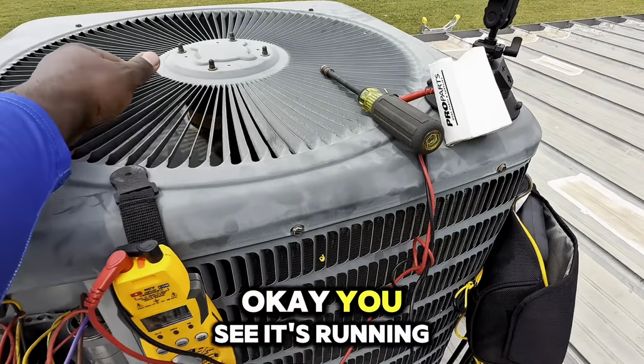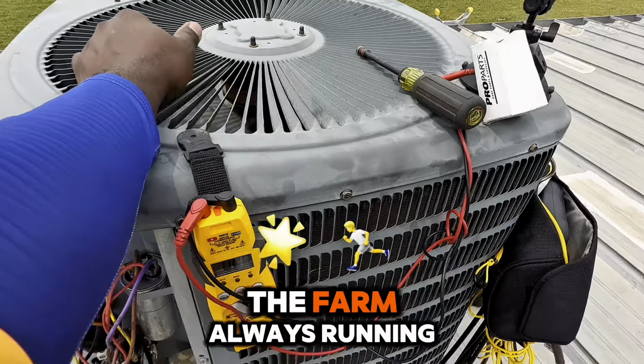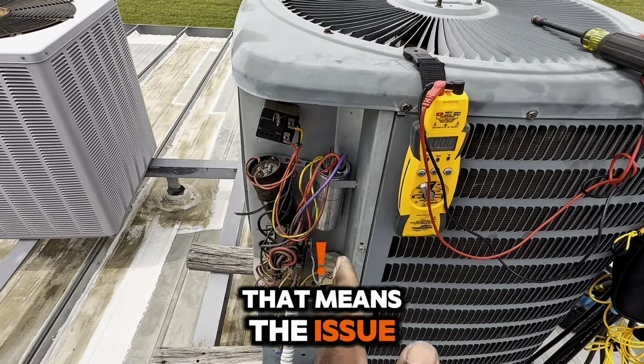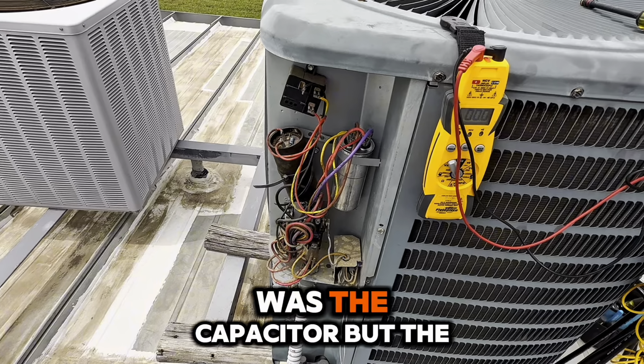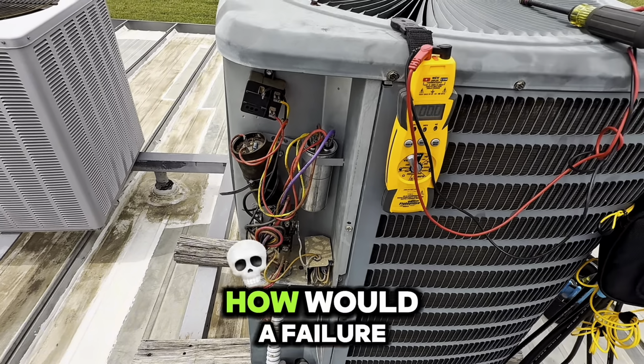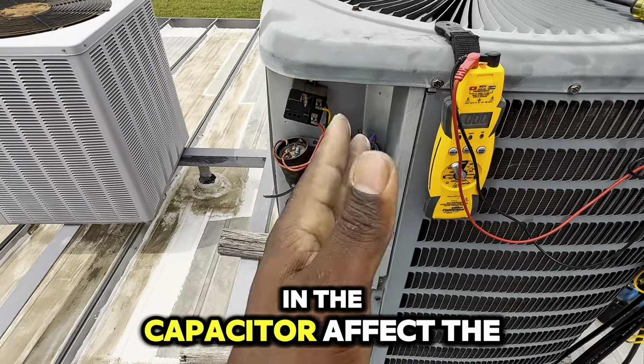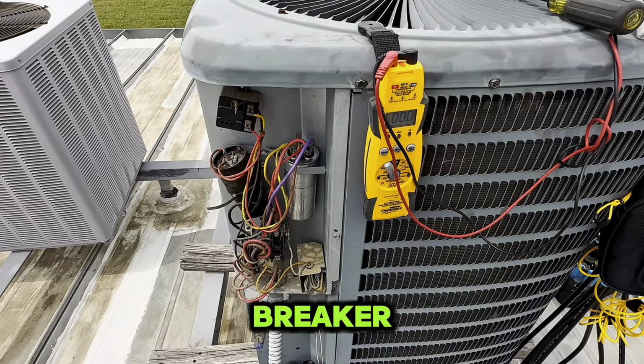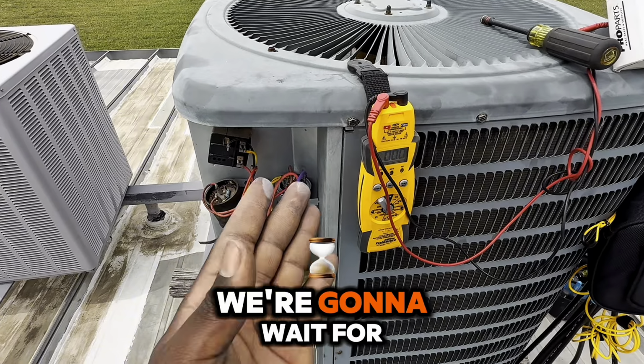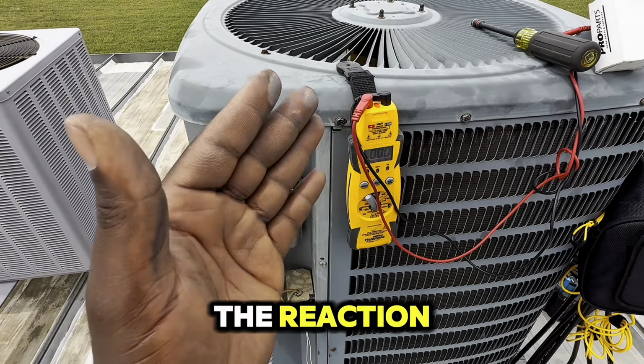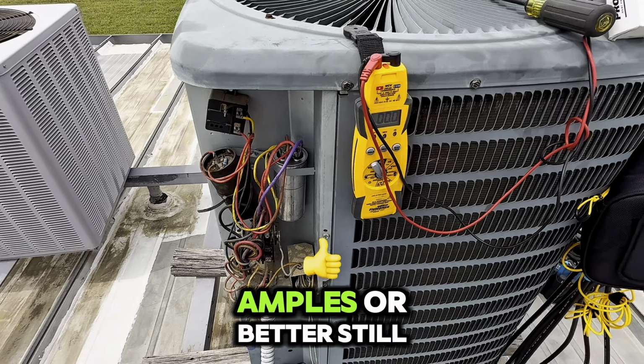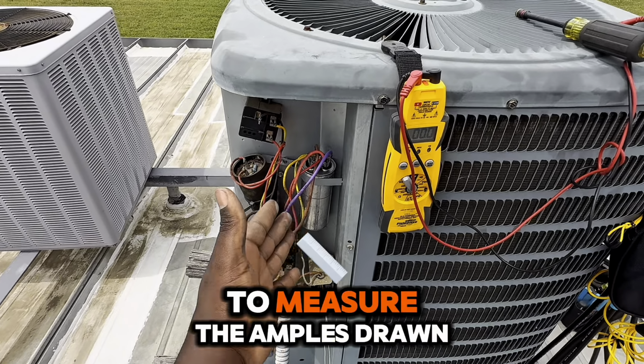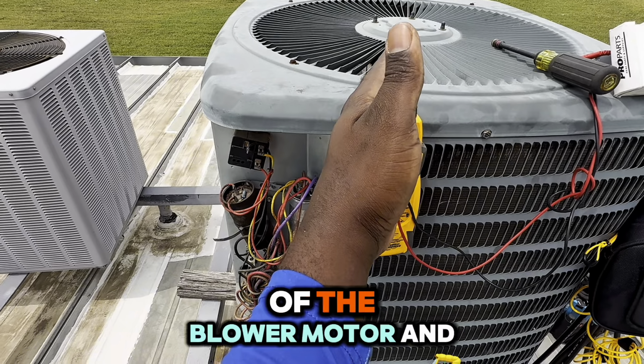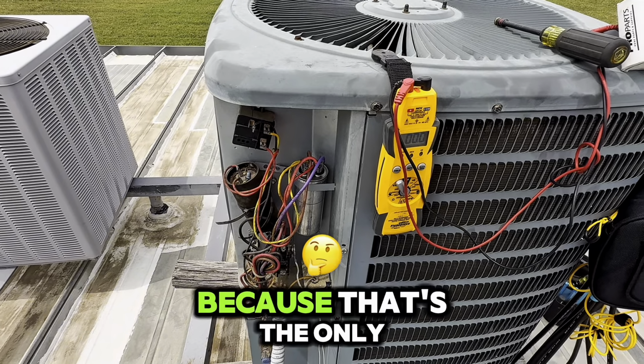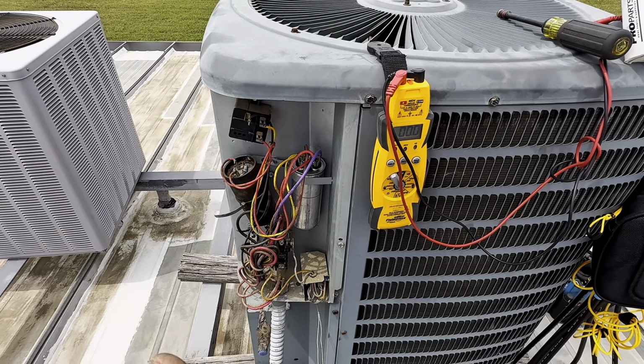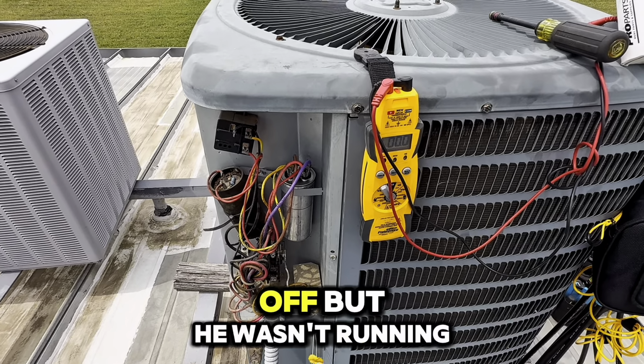Okay, you see it's running. The fan motor is running. That means the issue was the capacitor. But the question is, how would a failure in the capacitor affect the 40 amps breaker? So what we're gonna do here, we're gonna wait for some time to see the reaction. Maybe with time, we're gonna pull higher amperage, or better still, we should be able to measure the amperage drawn by the blower motor and the compressor, because that's the only thing that can actually trip the breaker off.